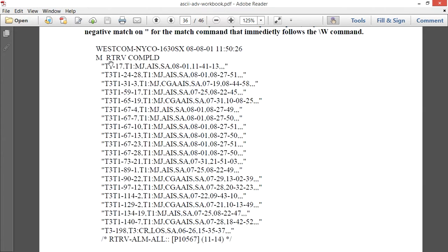So what we're going to use to start the line is RTRV. So we're going to match on RTRV, which was at the very beginning, which is actually a response to retrieve all alarm. So this whole thing is a response from a device whenever we send retrieve alarm all. And it gives us this big chunk of data. If you have alarms that are standing in TMON, and for some reason the ASCII message to clear it didn't come through or had been missed, this command here will only return what's currently standing.